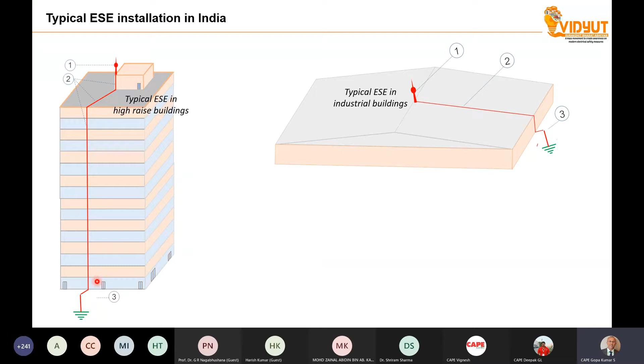Also for industrial installations, imagine there is a large industry - at the top of the building there is a rod, a down conductor, and an earth electrode. The danger again here is that in high-rise buildings, down conductors are always routed through some shaft, especially the electrical shaft, along with the electrical wiring. One classic example is my own building.